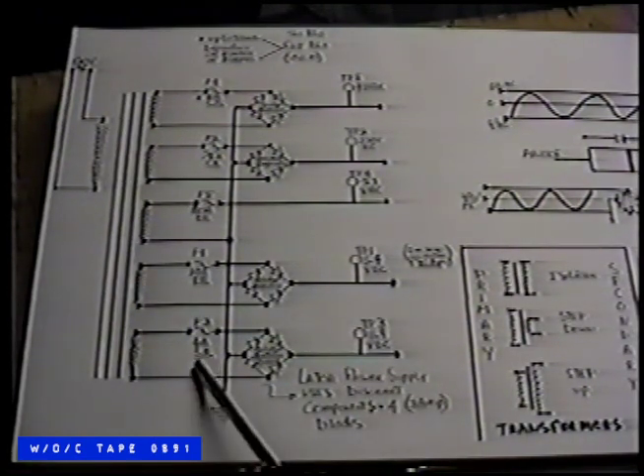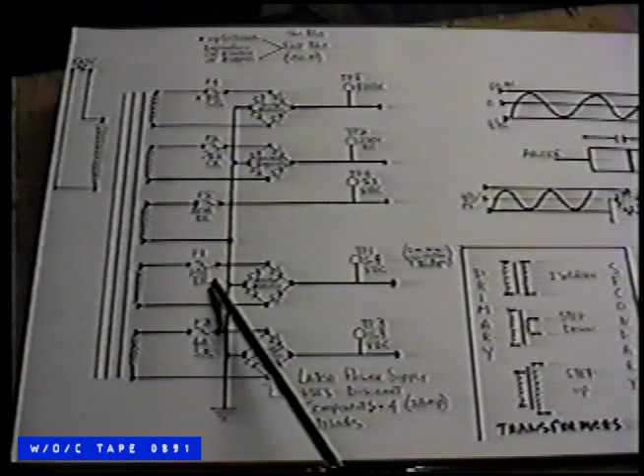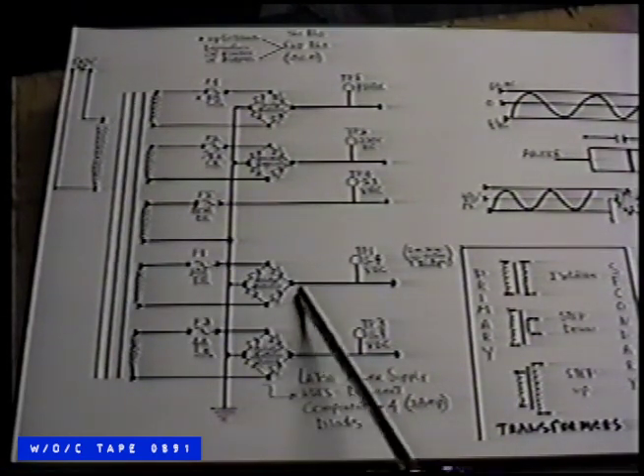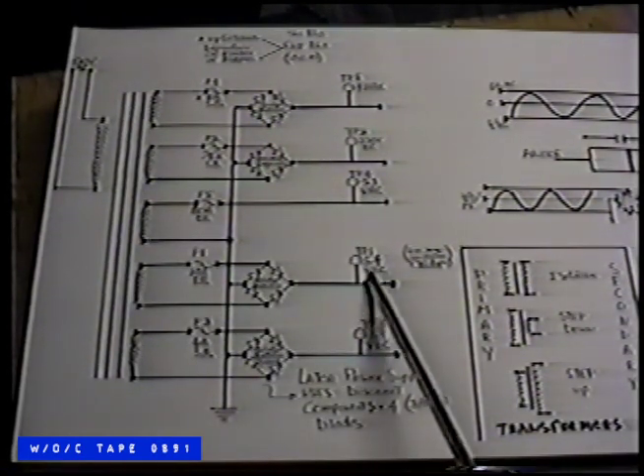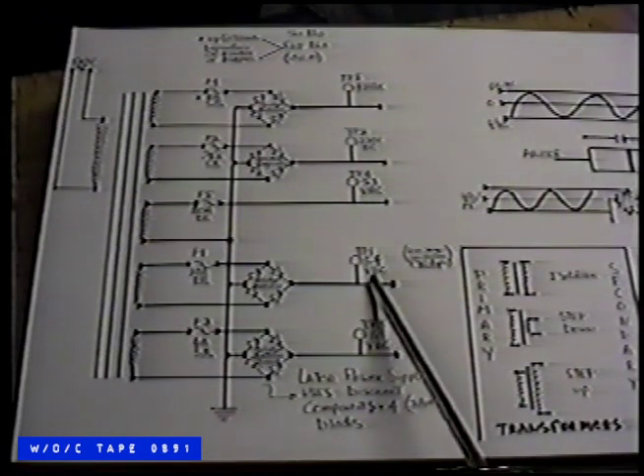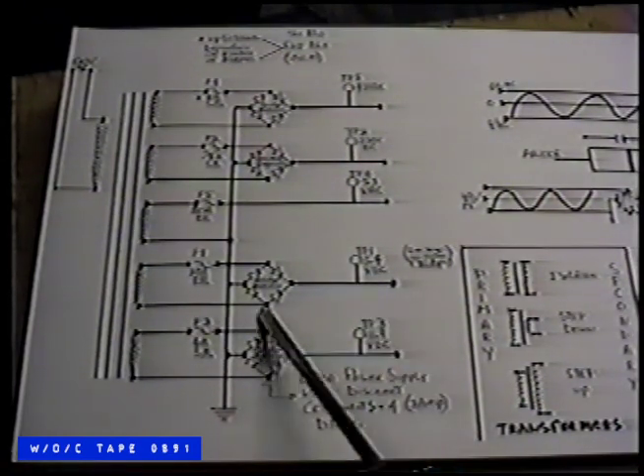That's usually on your general illumination, like you see here, and down on the bottom on the 11.9 voltage is also a slow blow. A fast blow here is on your 5.4 DC voltage for your controlled lamps.